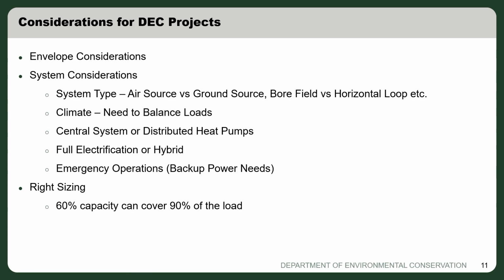And the climate matters. As Indu mentioned, you're using the ground as a battery. If you go up in the far north, your heating loads are going to be drastically greater than your cooling loads. If you don't know the subsurface strata of the area and you predominantly pull heat out without rejecting any back in summer, you could lose the efficiency of your well. So in a lot of cases we'll actually downsize the geothermal system to handle the cooling loads and use a hybrid system for the peaking loads, which I'll get to in a moment.